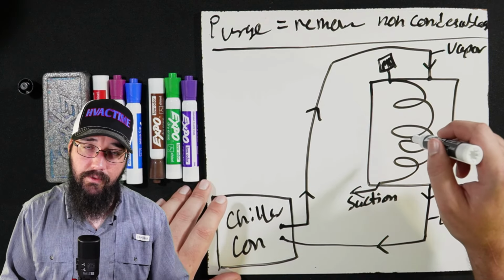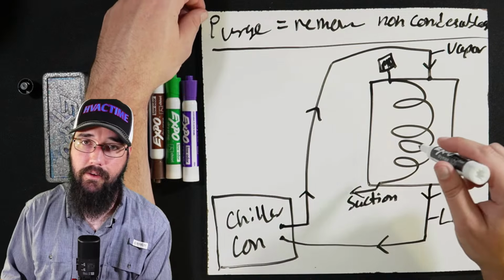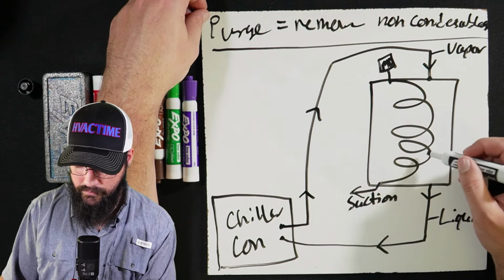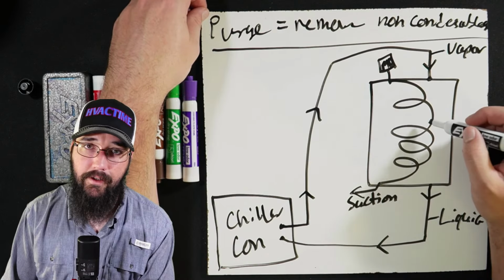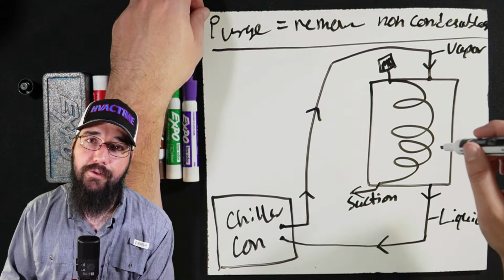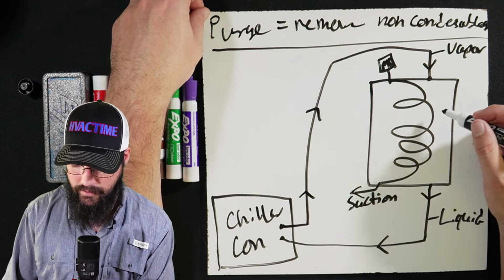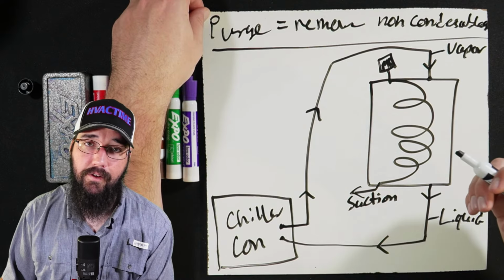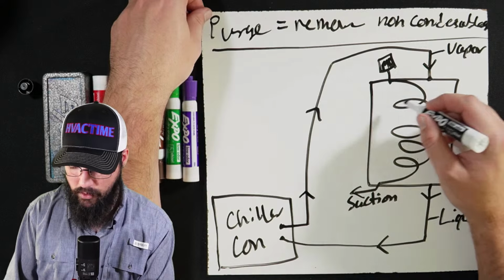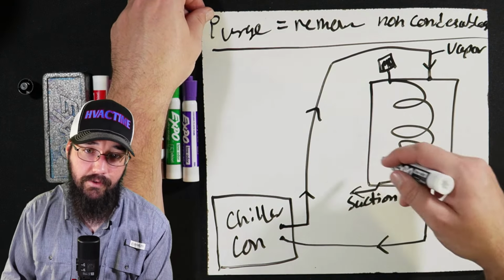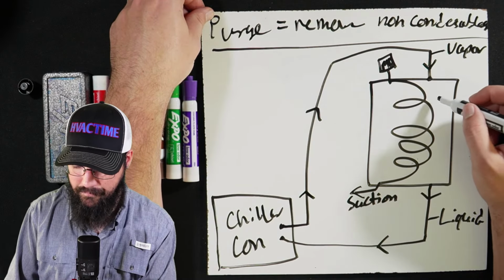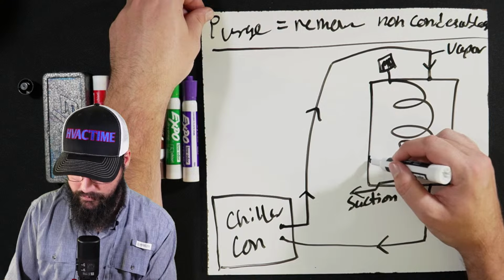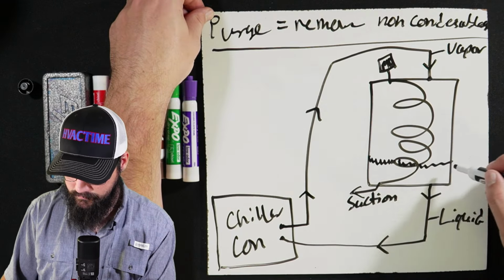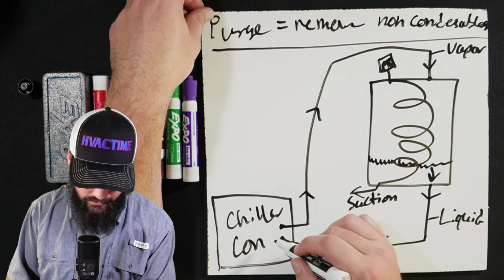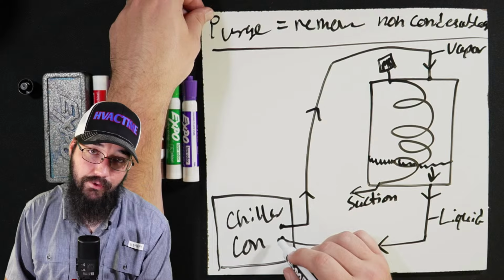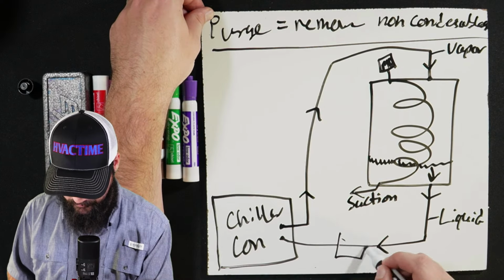as the purge compressor runs, the little recip compressor typically that these will have, as it is running, it cools this evaporator coil. The vapors that are in here, the refrigerant and moisture vapors begin to condense, okay? Because this evaporator temperature gets lower than their saturation temperature, and they begin to condense down. All this is part of the high pressure circuit, by the way, okay? So all this is within the chiller's high pressure side of the system. So as they condense, we start to collect that liquid here at the bottom, and then that liquid drains out the liquid line, leaving the purge evaporator and into our chiller. Now down here there will be a purge dryer.